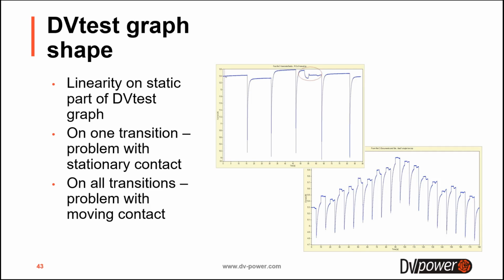So besides zooming the transition and analyzing the characteristic points during the transition, what you also need to pay attention to is what we call the linear part of the DVtest graph. It is the part of the graph before the transition starts. That part should be linear and the current should be smooth. If the current is not stable at that part, that means you have a bad contact somewhere.